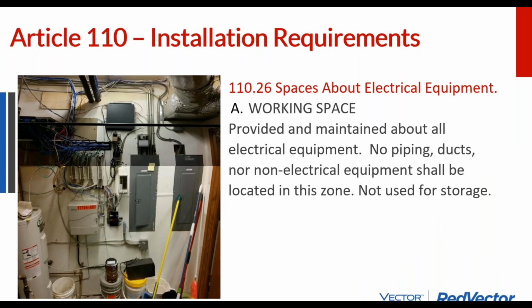All right, electrical spacing. So still in the first 100 section, the spacing around the equipment cannot be shared with any other spacing. So it has to be dedicated. So it may look like this room is a mess, but actually, if you can draw a rectangle around your dedicated electrical space, it only requires 6.5 feet from the ground. And so that air conditioning duct is actually outside the 6.5 foot height requirement. And so even though it's above the electrical equipment, it has enough clearance to be fine. Similarly with that hot water tank, that has some plumbing. It looks like there's a gas line, but it's still kind of off to the left.